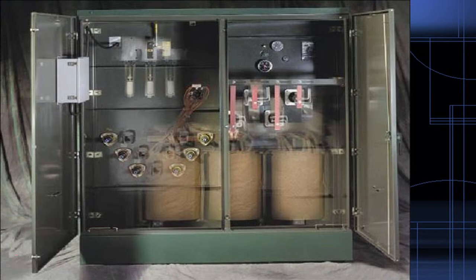So your transformer is typically put into an enclosure, a big metal box, in this case, a big green box with doors. And in this case, you'll probably see this outdoors. So this will be a 3R enclosure. So the enclosure has to be rated for the application. Your gray boxes that we showed, they'll have vents on the top. We got to think about heat. There will be heat that's generated.